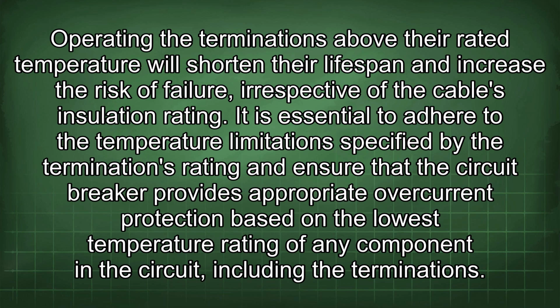Operating the terminations above their rated temperature will shorten their lifespan and increase the risk of failure, irrespective of the cable's insulation rating. It is essential to adhere to the temperature limitations specified by the terminations' rating and ensure that the circuit breaker provides appropriate overcurrent protection based on the lowest temperature rating of any component in the circuit, including the terminations.